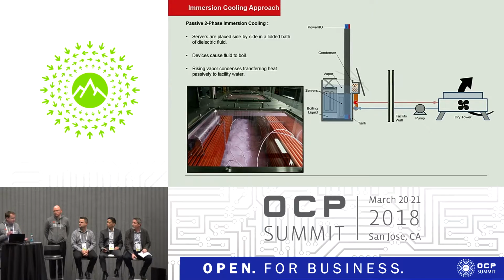I just wanted to make the point, for those who may not be familiar with the technology, that these tanks are serviceable. They can be opened during operation, and hardware can be removed and swapped just as it would be in a conventional rack. It tends to come out of the tank completely dry, similar to the way it would in a vapor degreaser, so hot swapping is a perfectly legitimate procedure for two-phase immersion.